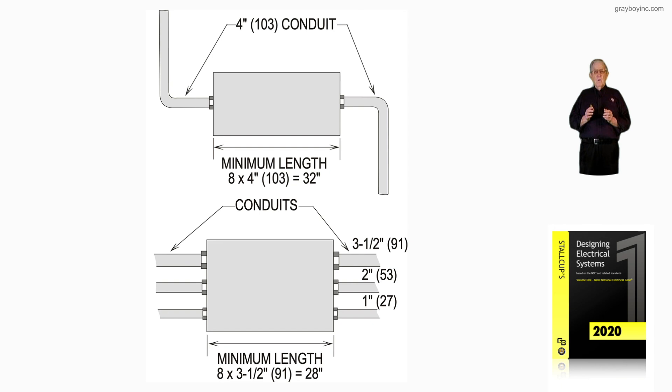So we're looking at a straight pull here, and that's what this figure is illustrating, a straight pull based upon eight times the largest conduit coming into the box on either wall.